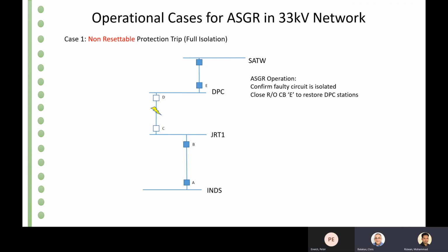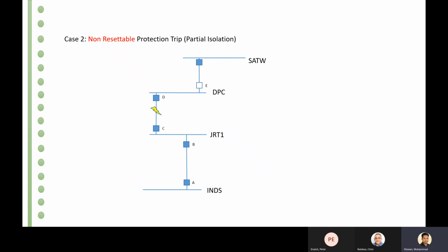Okay. Right. In case 2, if there is a fault between the circuit of JRT1 and DPC, and only one circuit trips from the feeding end, which is C. So in this case, first ASGR will isolate the faulty circuit by opening circuit breaker D. Once it is confirmed that the fault is isolated, then supply will be restored from SATW substation.